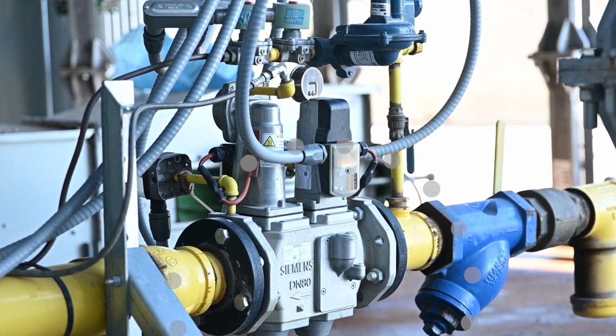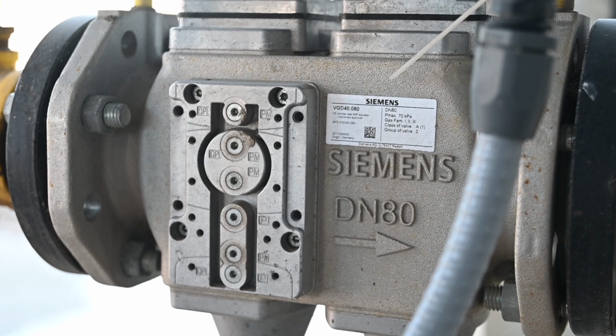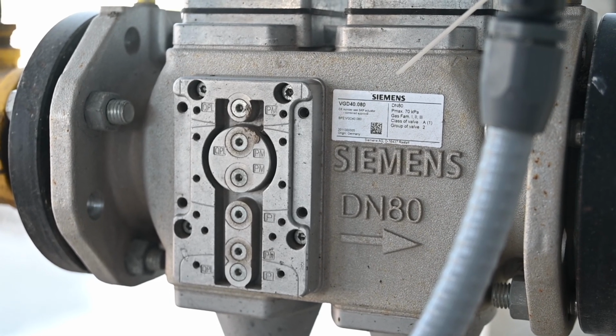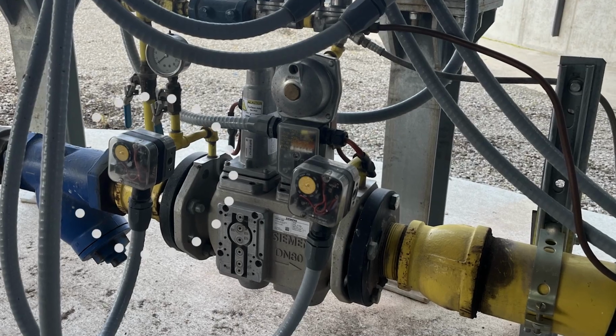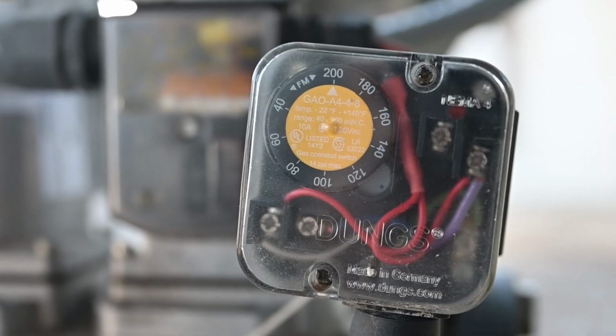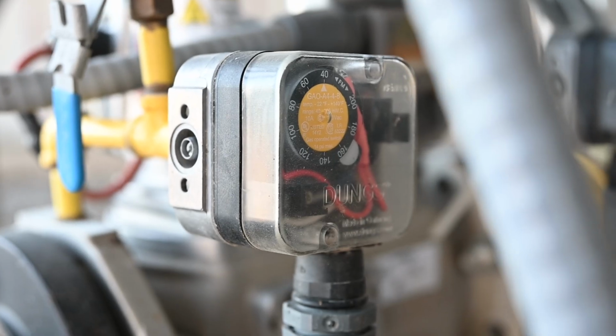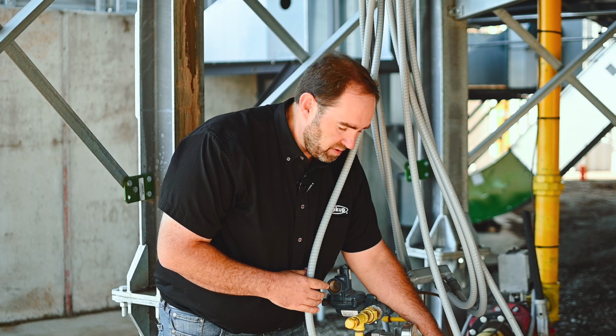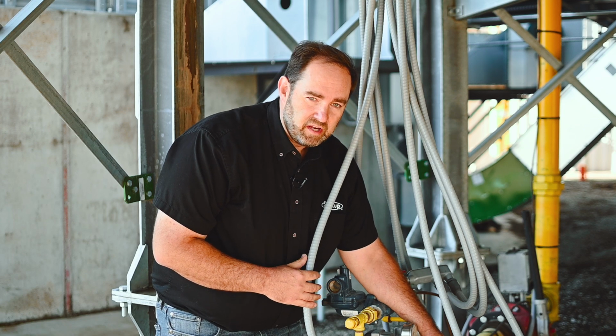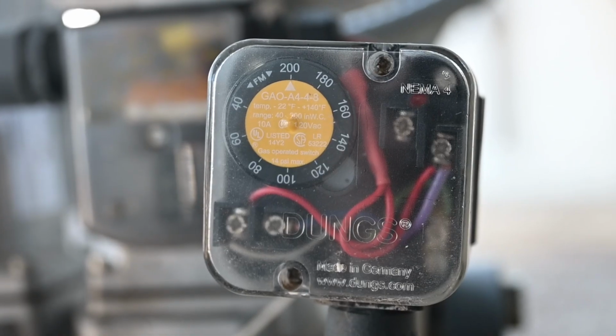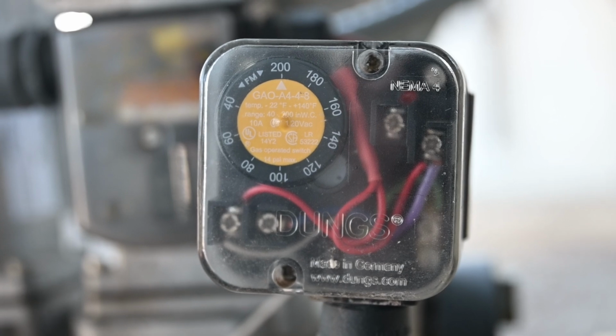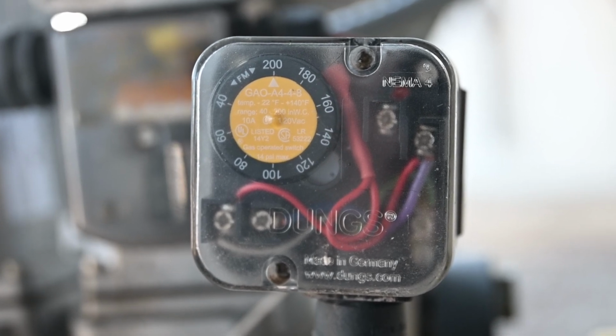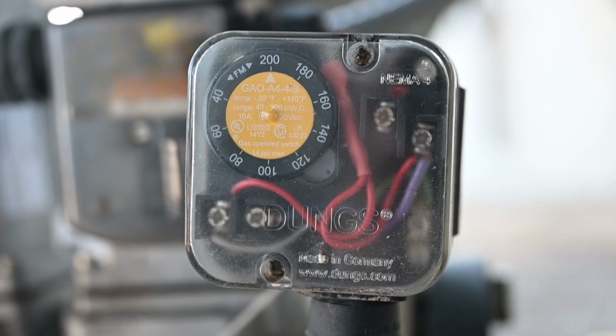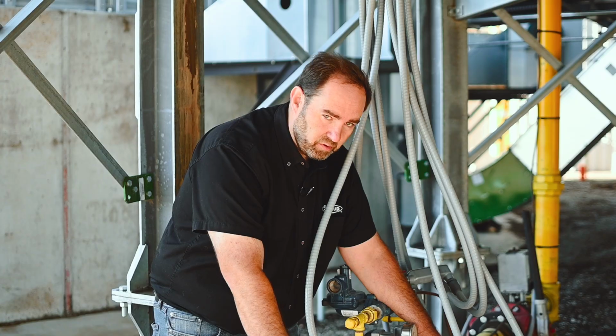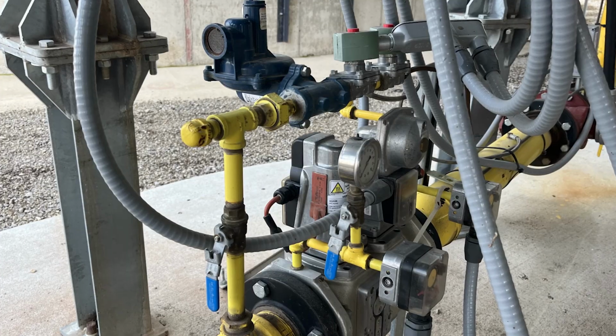The next item here, we call the Siemens solenoid valve block, and that has many components in it, so we'll take a look at what all of them are. The first thing we come to is a low pressure switch, and this just indicates that we have enough gas pressure to run the dryer. This dial here will be set between 40 and 200 inches of water column. The low pressure switch should be set at 40 inches of water column. There is an indicator light on here, so when main power is on and we have adequate gas pressure, the light will be on. If the light's off, then we might not have enough fuel. Maybe the quarter turn shutoff valve hasn't been turned on, something along those lines.